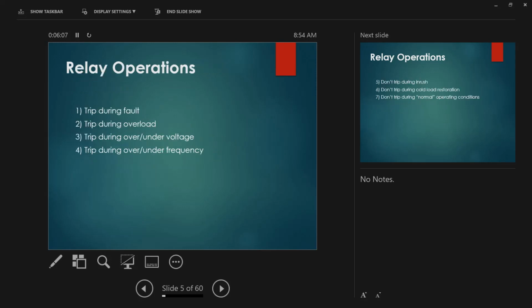So, relay operations. As we continue, you can ask questions so that we can have some dynamic discussion. A relay is designed to trip during a fault, trip during overload, trip during over and under voltage, and trip during over and under frequency.